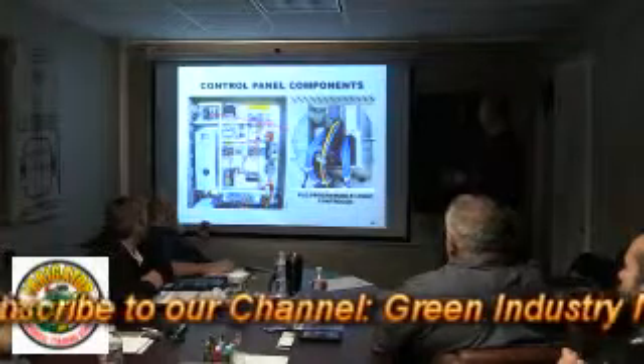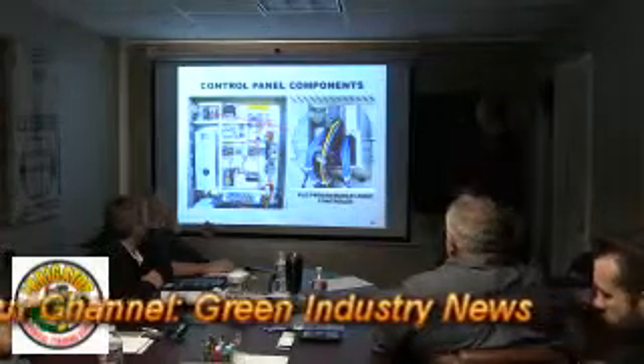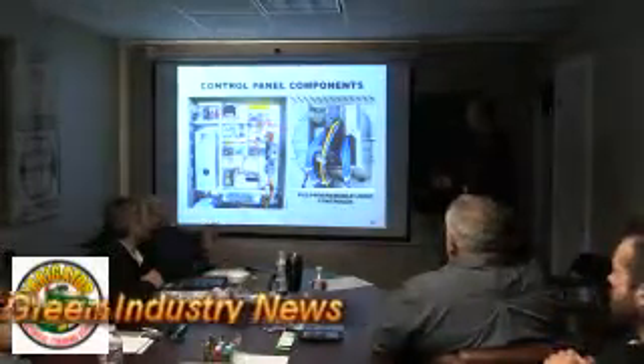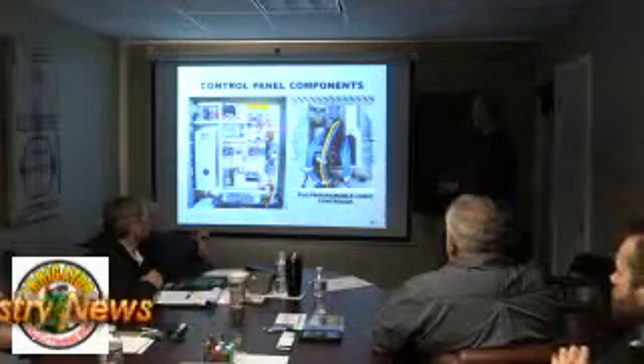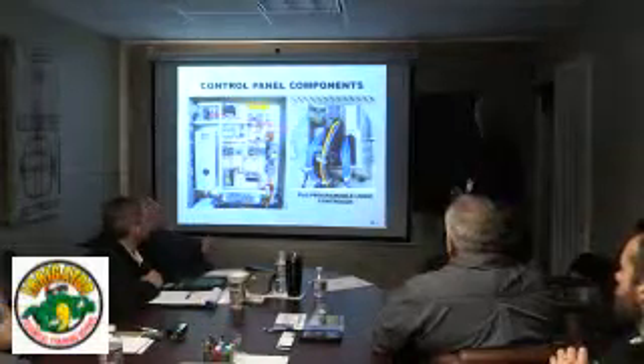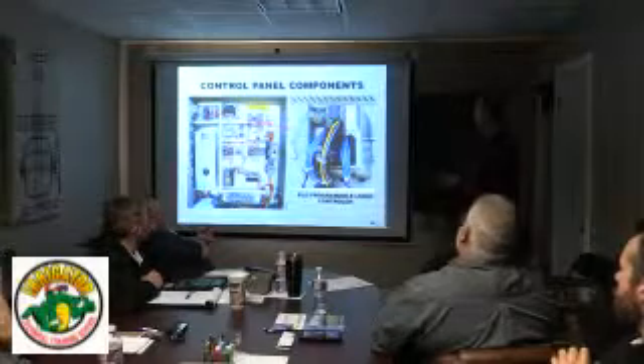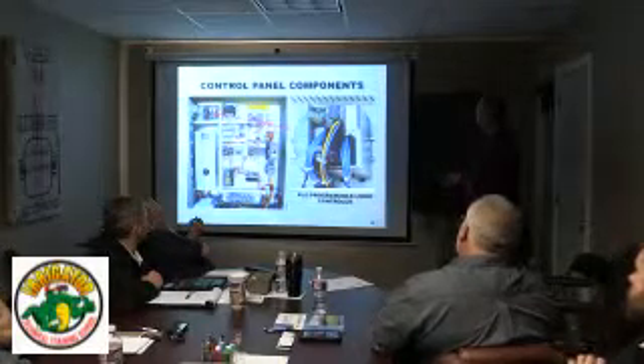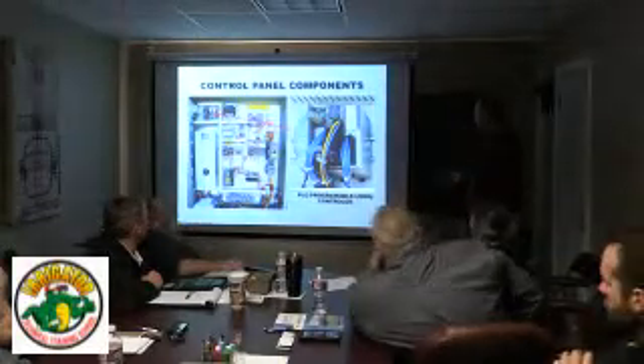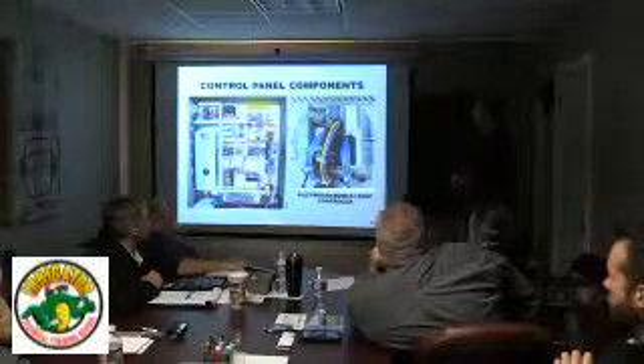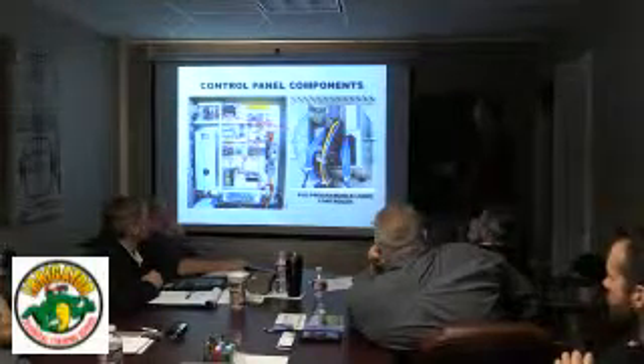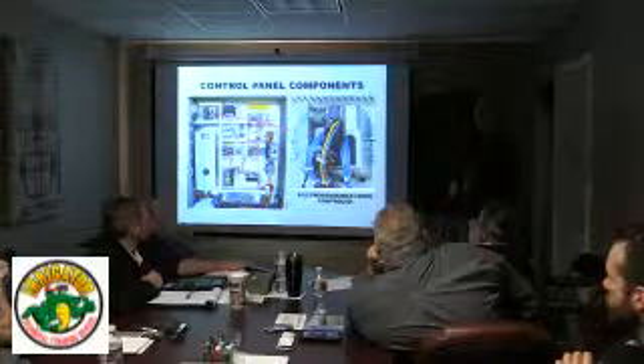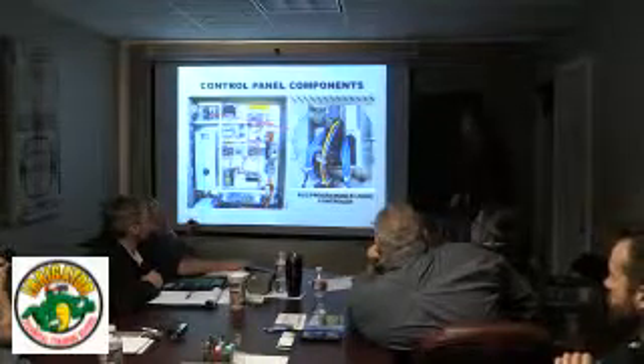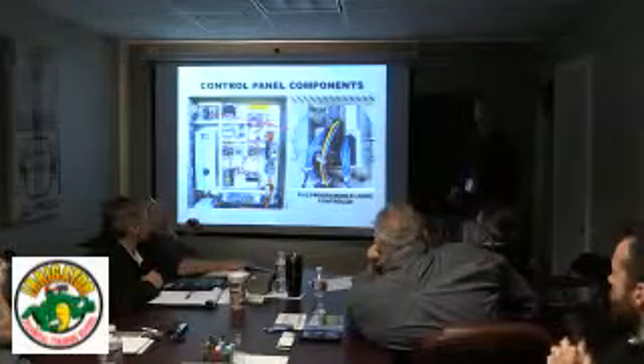Some of our fault lights, we might use yellow or an orange, or coils to contactors if they're 120. We use a dark brown. We have a black coming into here, which is probably like a common supply for several of these, and then we'll have a dark brown going into the coils on a contactor or something.